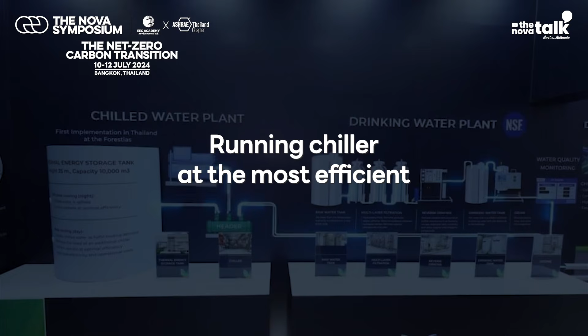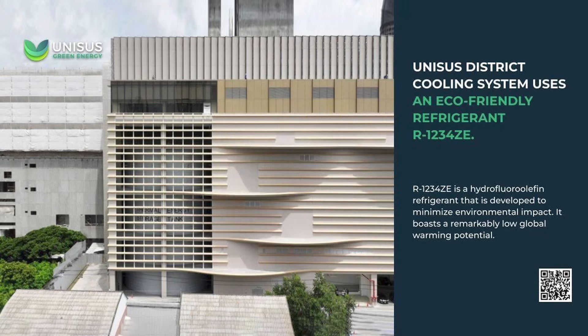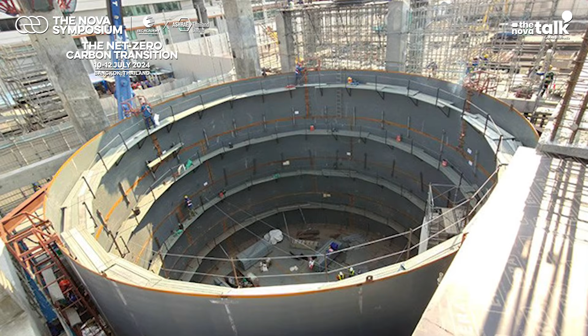It was not in my question as planned, but you mentioned thermal storage. I think this is maybe one of the keys of designing a district cooling system. Can you suggest or advise more on that? Yeah, so the thermal storage tank is just simply like an electric battery, but it's more of a thermal battery. What we're trying to do here is use the chillers when it's most efficient, and then extra cooling that's not required to be supplied to the buildings can be stored in the thermal storage tank. And then we would turn off the chillers, or maybe fully load the chillers at other times, and use the thermal storage as another chiller basically, and send the chilled water that has been put in that thermal storage to the building.